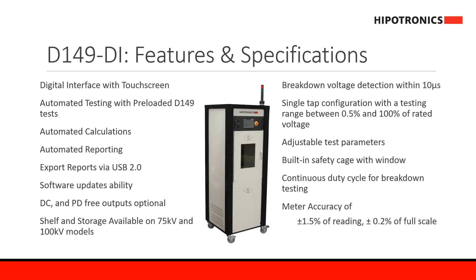Although the system comes with pre-loaded D149 tests, the operator can also adjust any of the test parameters. Both versions of the system — the smaller version and the larger 75kV version — come with a built-in safety cage window, and it's designed with a continuous duty cycle for breakdown testing. This unit also has one of the highest accuracies in the market, at 1.5% of reading plus/minus 0.2% of full scale.